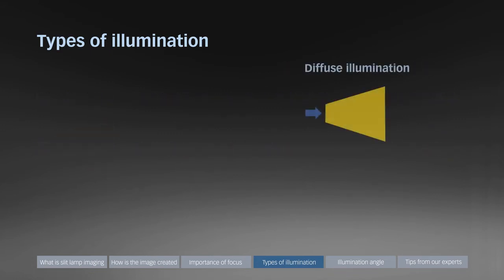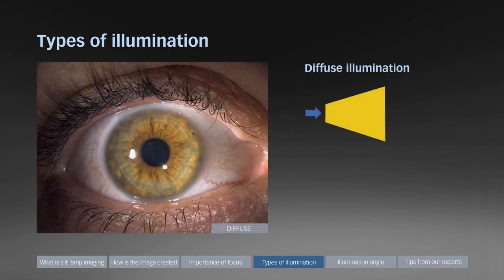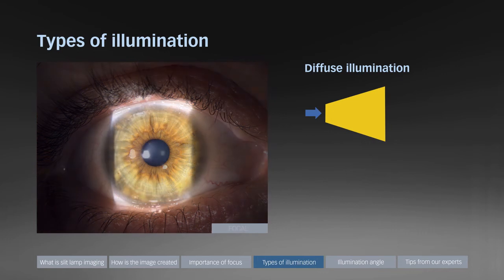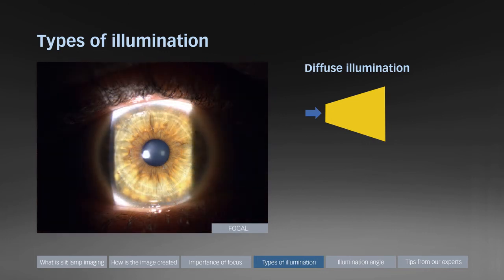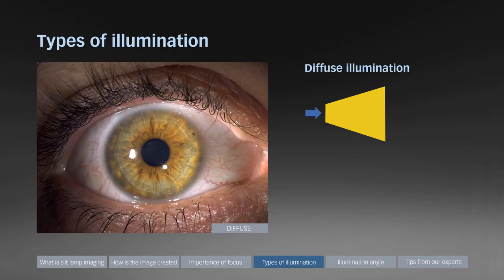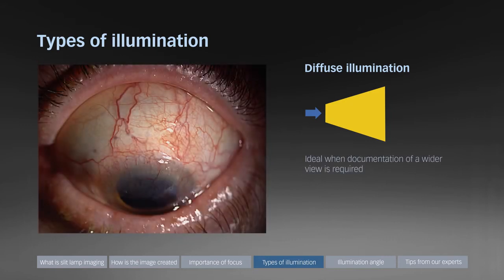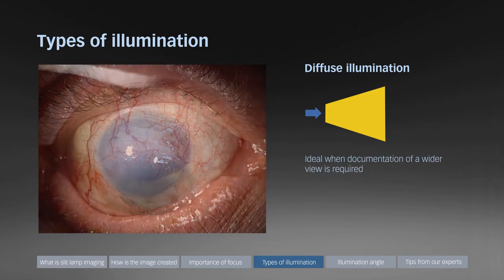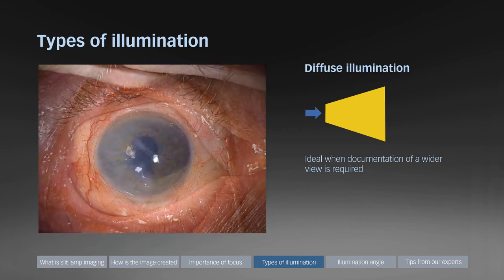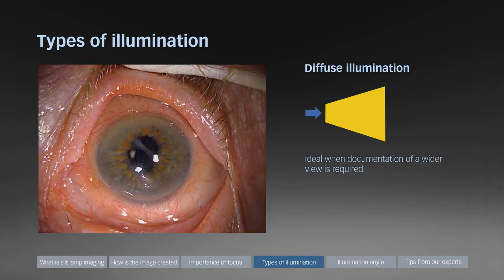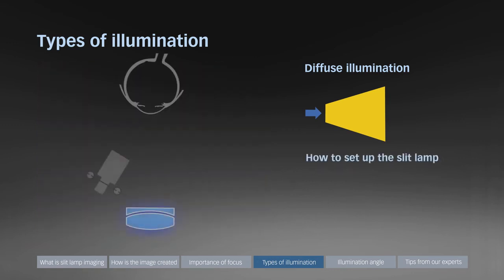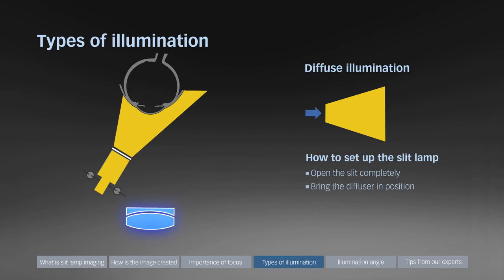Diffuse illumination provides even light distribution. For comparison, the same eye with direct focal illumination, and here the diffuse illuminated version again. Diffuse illumination is ideal when documentation of a wider view is required. To set up the slit lamp for diffuse illumination, open the slit completely, bring the diffuser into position, and use a small amount of background illumination.